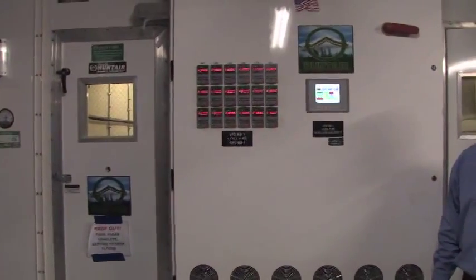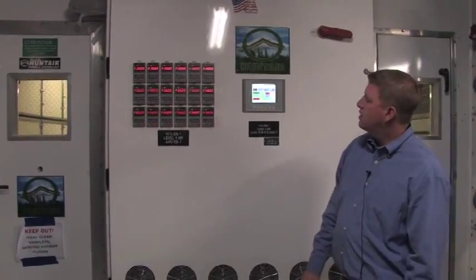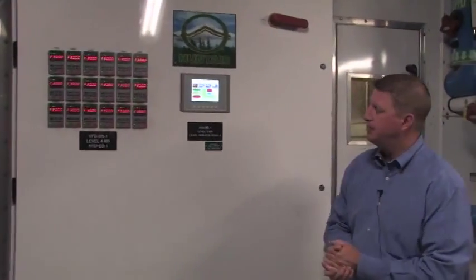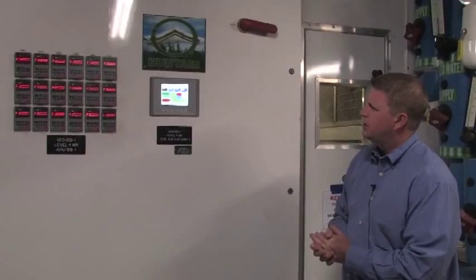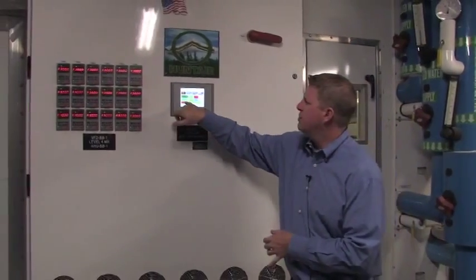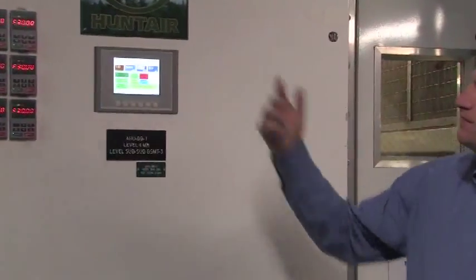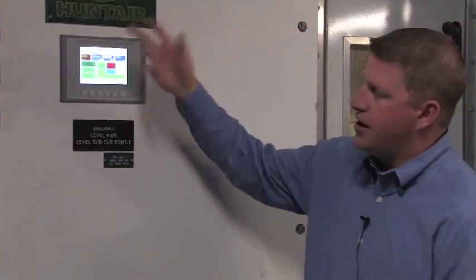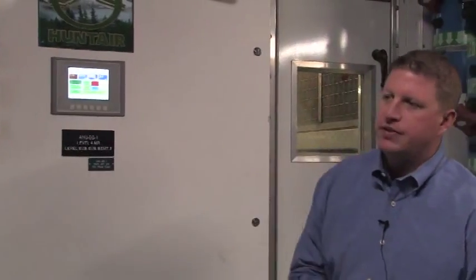And enable CFM control is going to take that last command of 20,000 and go down. Yep. So if I go enable CFM control, it's going to drop it back down to 20 hertz. Exactly. And if I put it to 30, yeah, exactly.